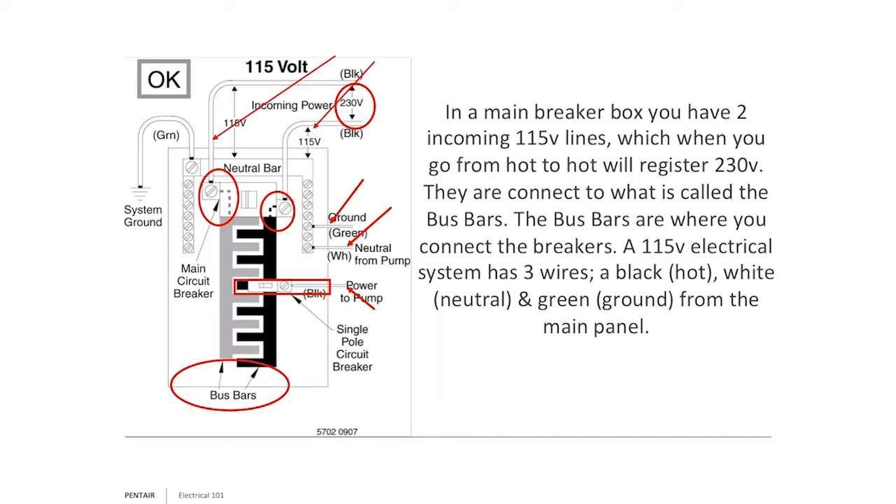You'll have your power line, your neutral coming back from the power supply — the neutral completes the circuit for the device and ensures proper grounding. You'll also have a ground green wire. What the ground green wire does is protect the equipment housing — for example, if a computer's power supply leaks voltage to the frame, the frame is grounded so that stray voltage can be taken to ground safely and keep you safe. So you have a neutral bar where both your ground and your neutral are connected.